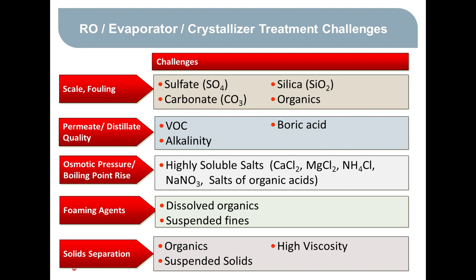And this is the deposit of low solubility salts on the membrane surfaces or on the heat transfer surfaces, which impede the thermal process or the osmotic process in an RO system. So scaling and fouling are certainly things that we're concerned about. As I mentioned, with the recovered water, the distillate or the permeate, we sometimes have to be concerned with the carryover or the volatilization of things like organic compounds or boric acid that could wind up in that recovered water and may have to be removed.